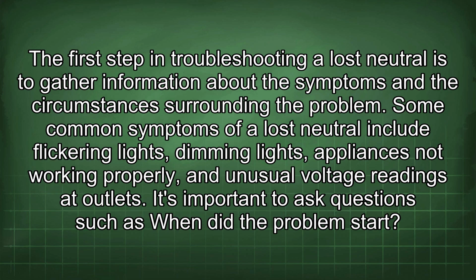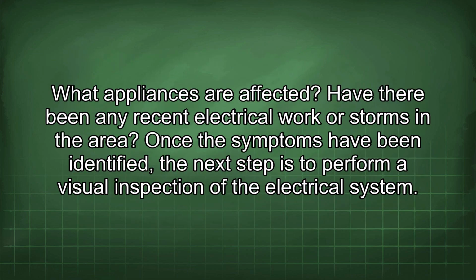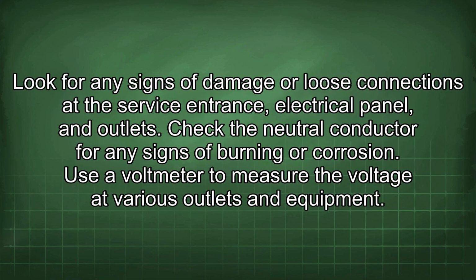Let's further discuss the diagnostic procedures and troubleshooting steps that can be taken when a lost neutral is suspected in an electrical system. The first step in troubleshooting a lost neutral is to gather information about the symptoms and the circumstances surrounding the problem. Some common symptoms of a lost neutral include flickering lights, dimming lights, appliances not working properly, and unusual voltage readings at outlets. It's important to ask questions such as when did the problem start? What appliances are affected? Have there been any recent electrical work or storms in the area?